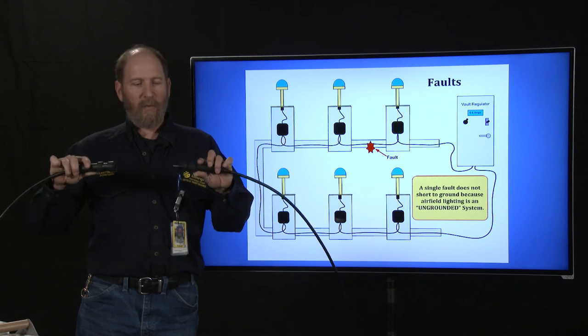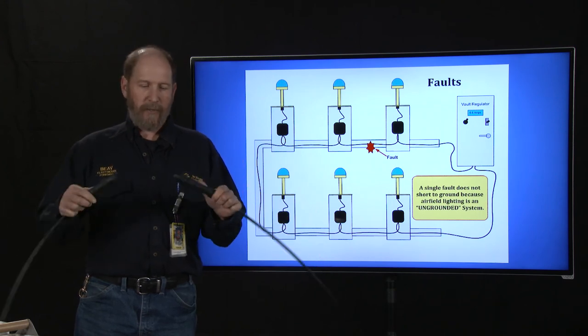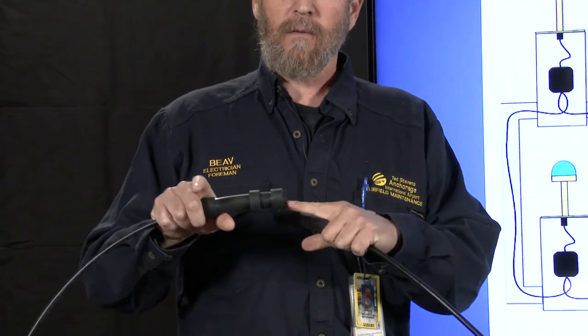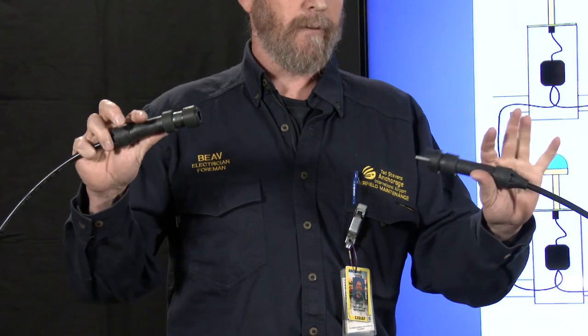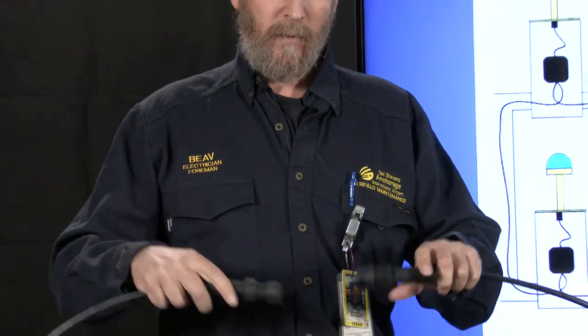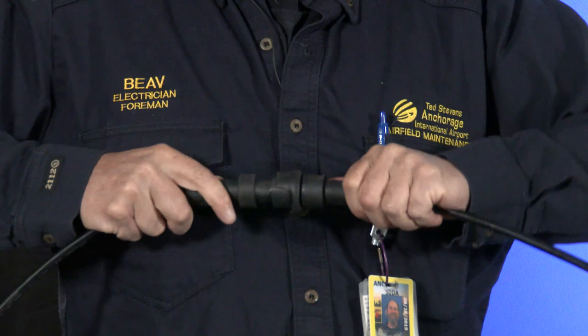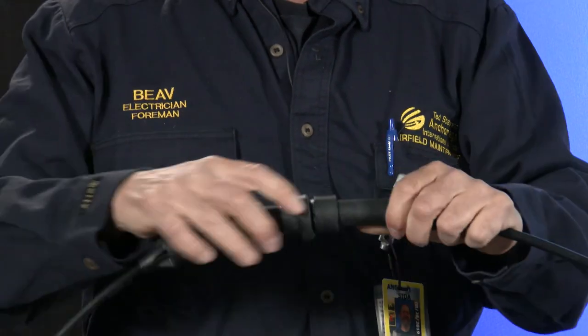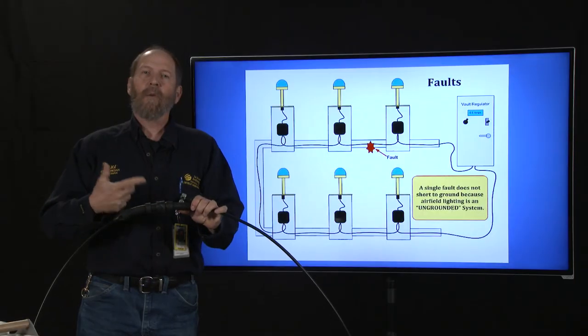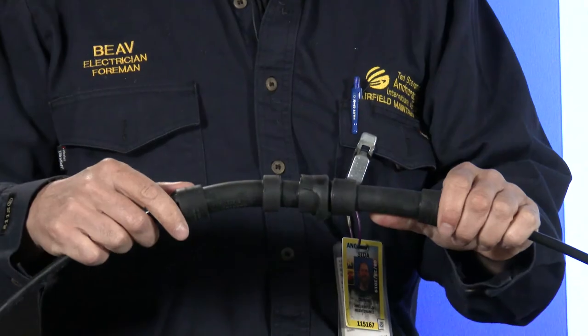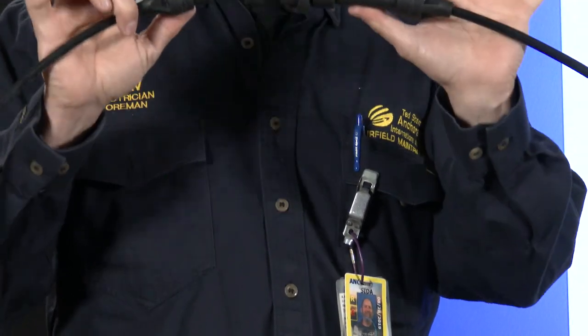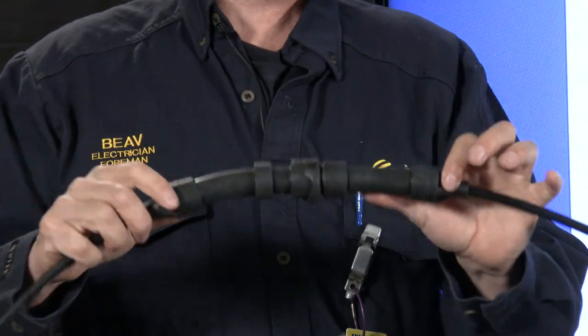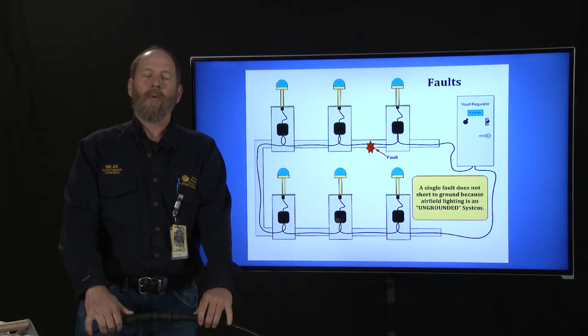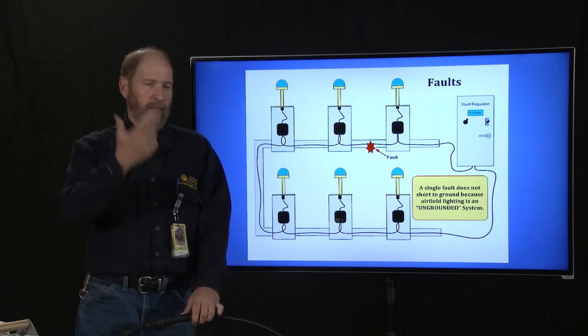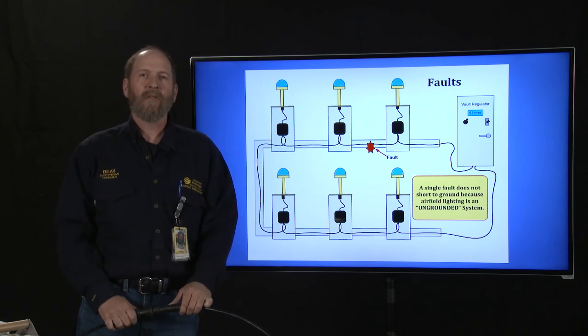These connectors here are the ones we use out on the airfield. We call them joy connectors. And they're real simple. It's basically just a male and a female connection in a rubber plug. That's pretty much all there is to it. They just mate together tightly, sort of a seal right there. Normally we'll put a little bit of rubber tape around them, maybe a little other tape. And that's good enough to put 5,000 volts on it. We can stuff that down in a can full of water and potassium acetate, hit it with 5,000 volts, and it's good as can be.